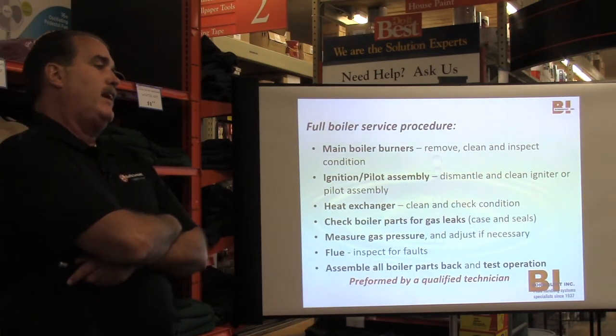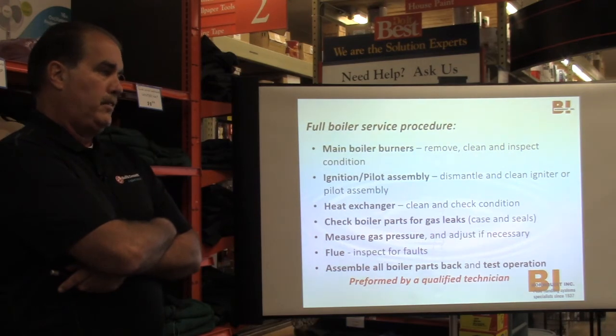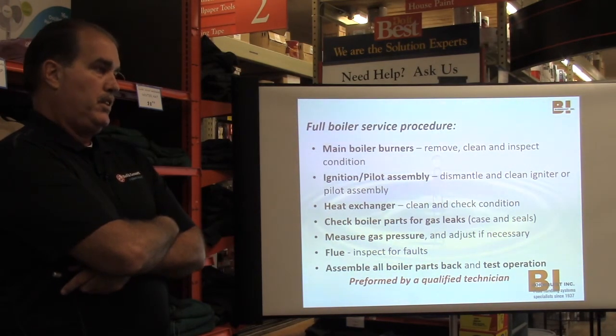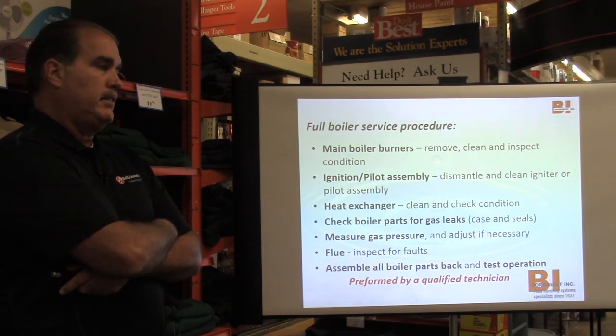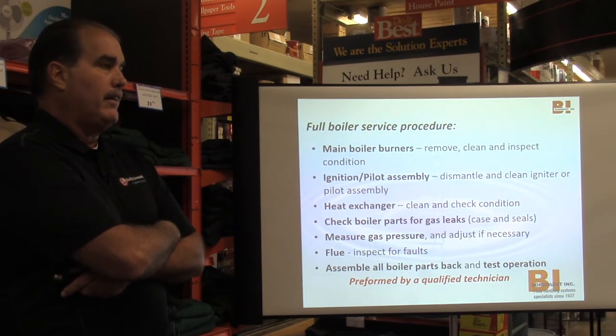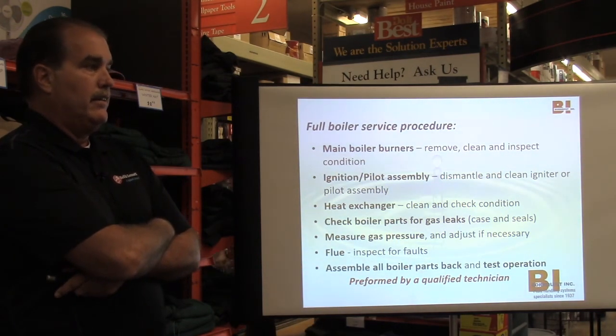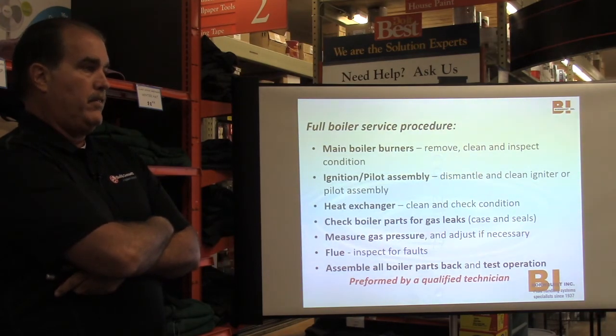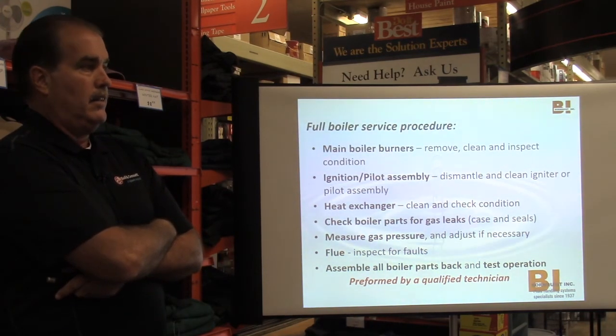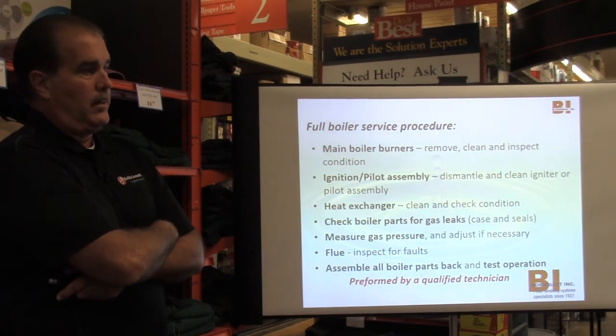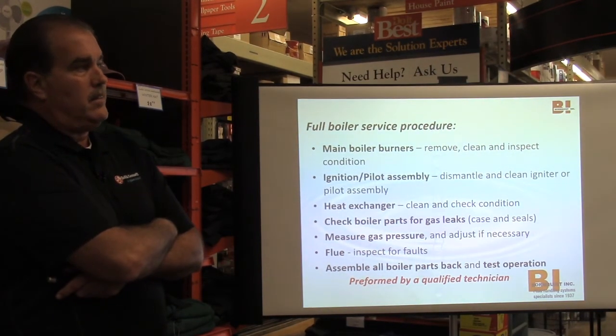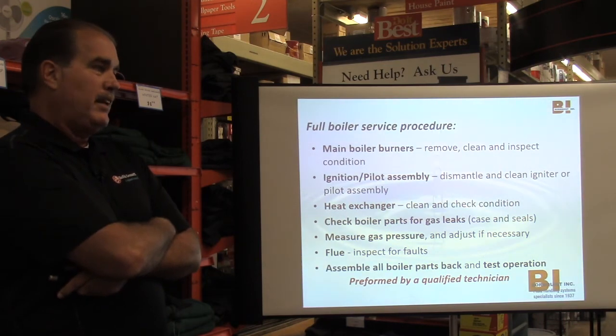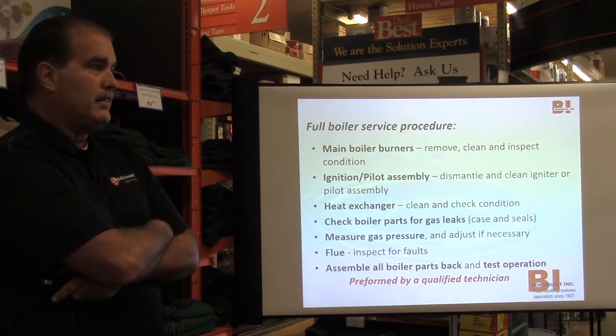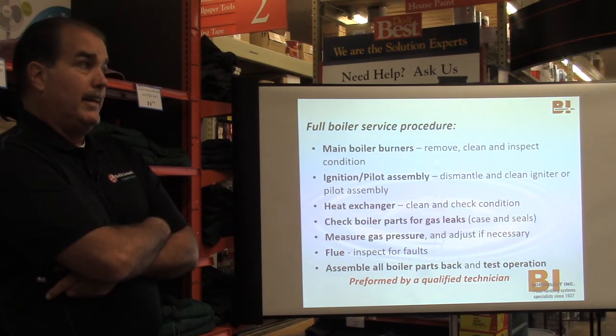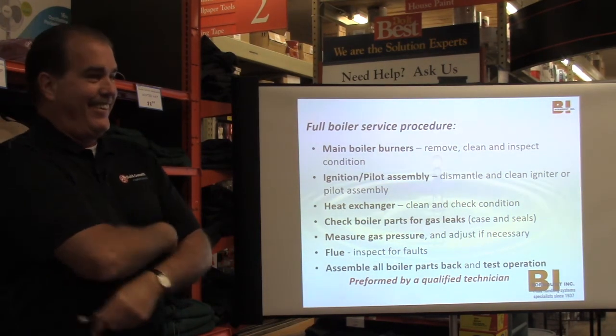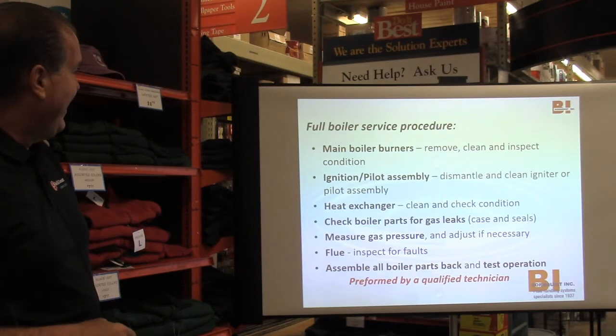The reason they're saying that is because sometimes the corrosion can happen right at the water line. Often you won't see it, but you're going to see it with the steam coming out at the top of the boiler. Yeah, because you don't necessarily see the steam if you're not looking for it. Right, and that's what they're talking about there. Plus, those boilers last like 25 years, a long time, but when they go out, they go out. Yeah, on Christmas Eve. Or 5 below.